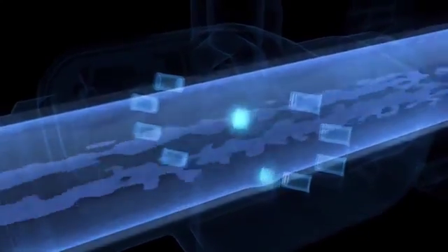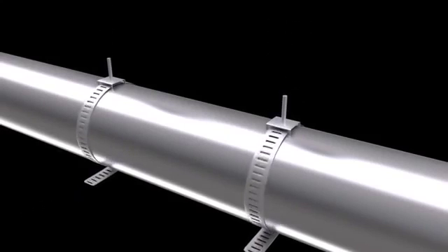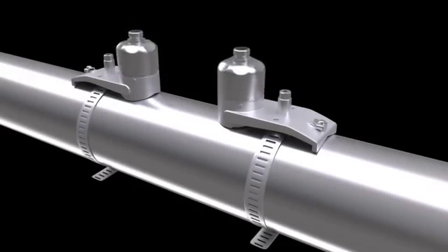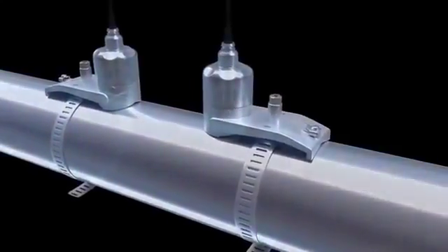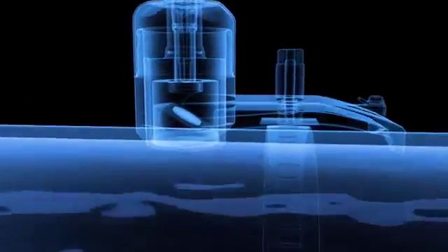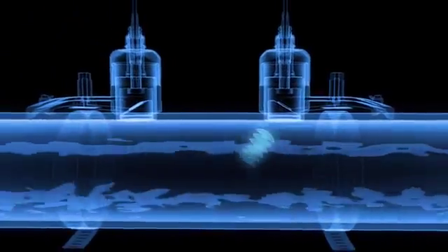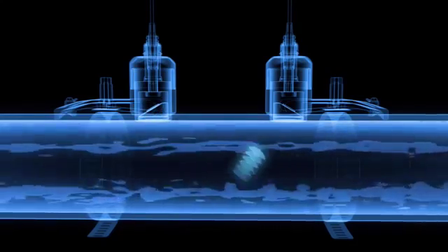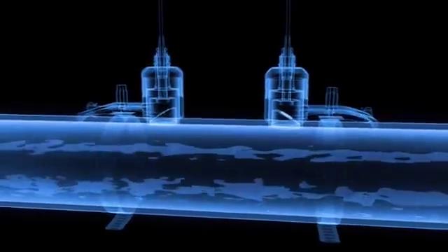For ultrasonic flow measurement, the sensors do not necessarily have to be fitted into the pipe wall. With a clamp-on system, for example, the sensors are fastened directly onto the outside of the pipe. They can be retrofitted at any time without interrupting the process. With clamp-on sensors, the ultrasonic signal is passed directly through the pipe wall and into the fluid. The signal continues through the fluid, is reflected on the opposite pipe wall, and then measured by the second sensor. In this example, with a two-traverse installation.